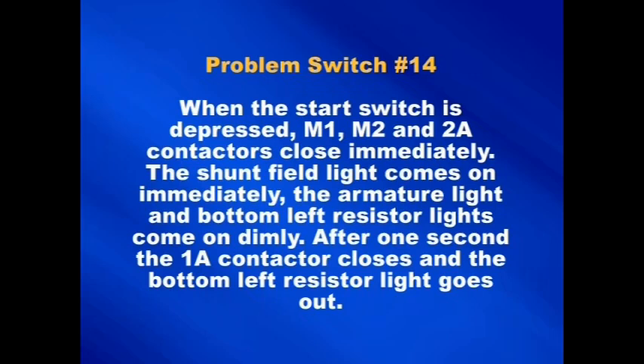When the start switch is depressed, M1, M2, and 2A contactors close immediately. The shunt field light comes on immediately, and the armature light and the bottom left resistor light come on dimly. After 1 second, the 1A contactor closes and the bottom left resistor light goes out.